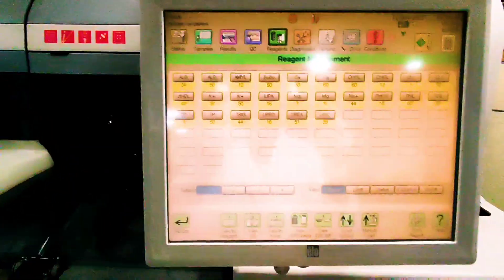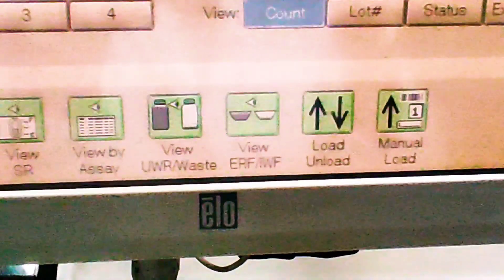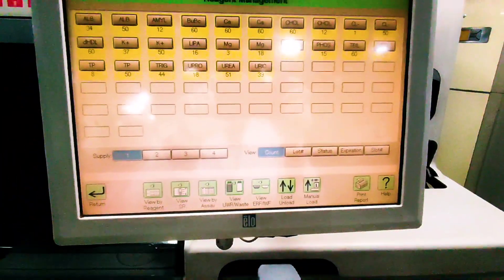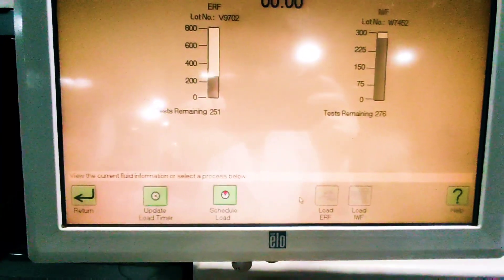To begin with the procedure, we first click on the reagents icon at the top, and after that, at the bottom, we can see another icon for View ERF/IWF. Click on it to know the status of currently stored electrolyte reference fluid in the system.